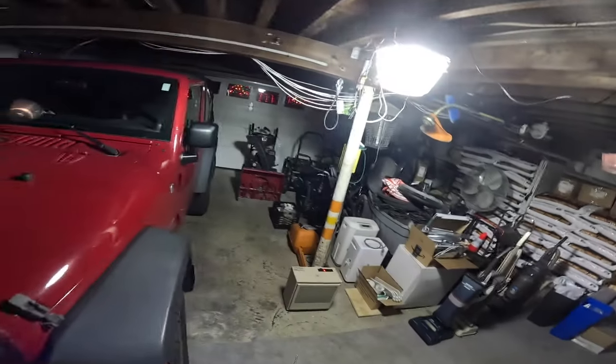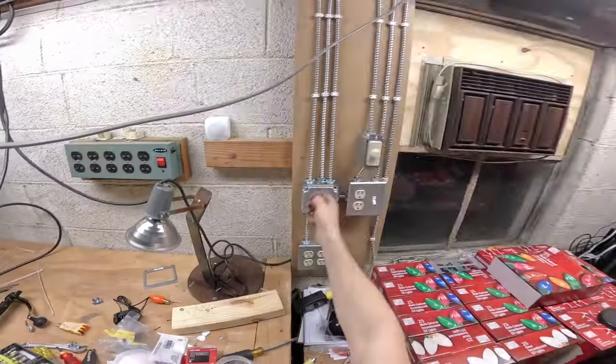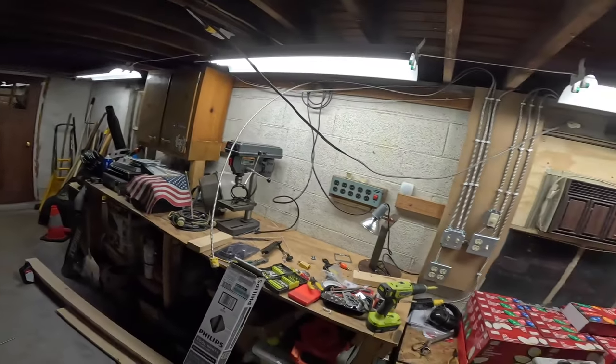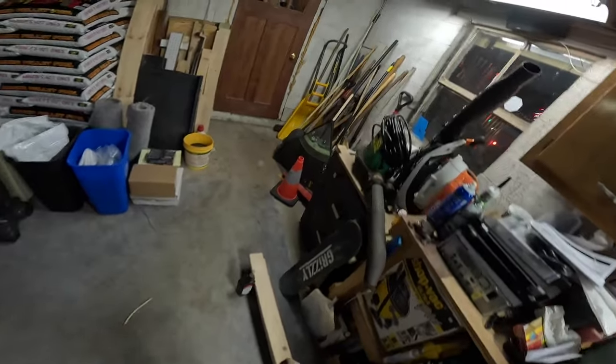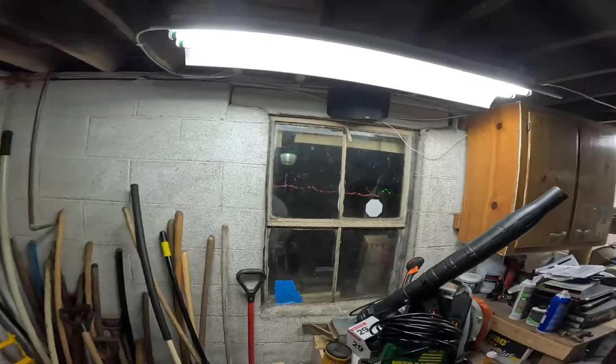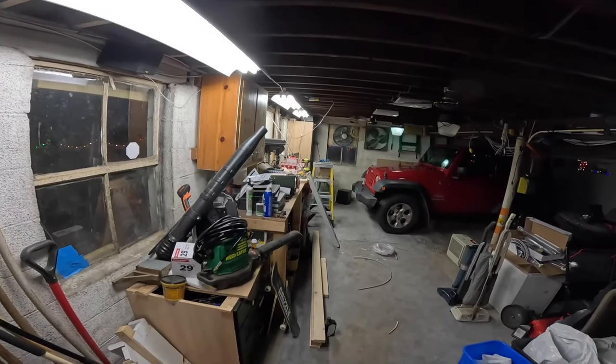All right, that's working, the fans are working again. This will take a minute to restrike, but I will move that back to where its new home is. Now let's see if we get sparks and flames or light. We get light. Beautiful. All three fixtures are operating properly.